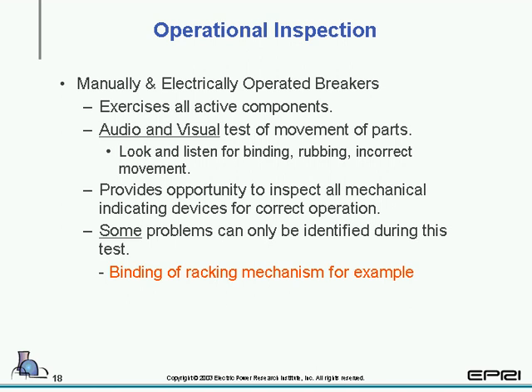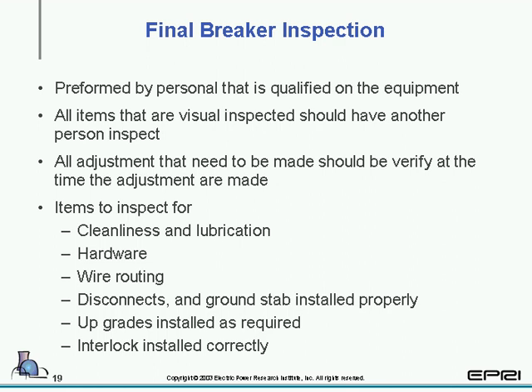One of the other items is operational inspection. It's very important, as we spoke about in the very beginning, that the technician performing the task is qualified. One of the main items that having a qualified technician look at the equipment is audio, as well as visual testing. And the very last item is binding of racking mechanism, for example. And then we have some items for final breaker inspection. Again, you want whoever is performing that task to be qualified. All the items are visually inspected by another person doing the inspection.